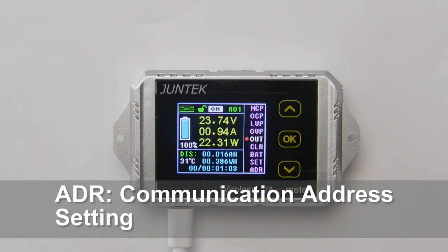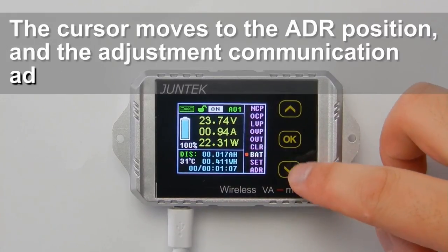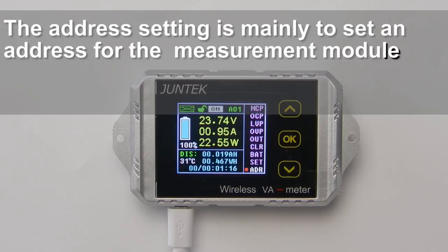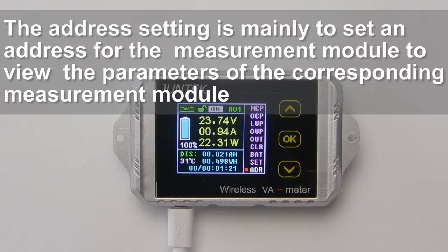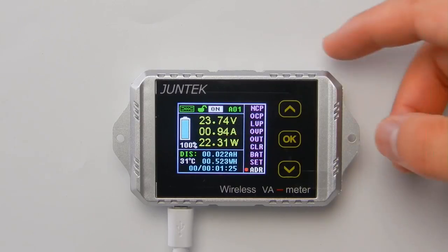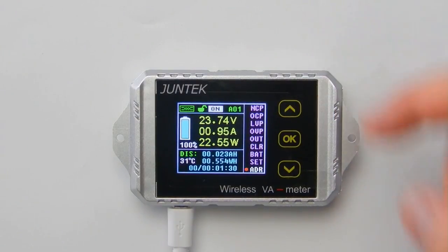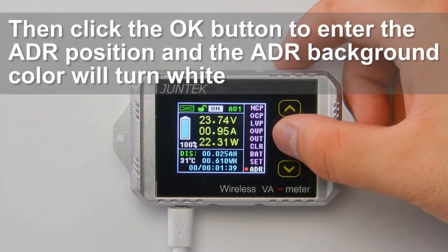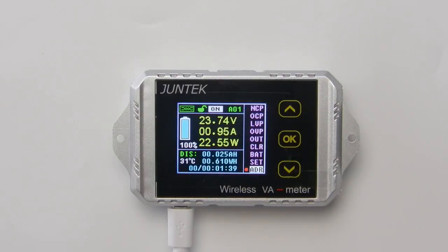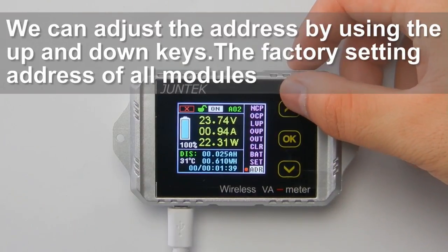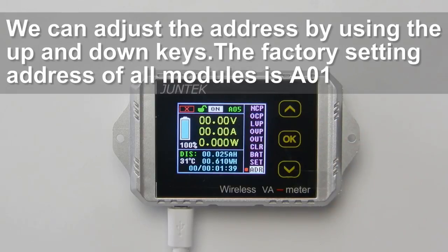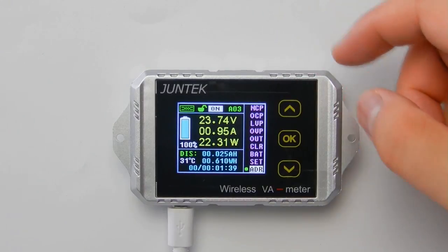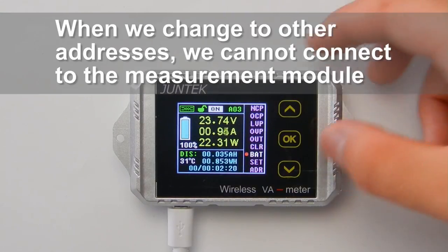ADR — communication address setting. The cursor moves to the ADR position and the communication address is set in wired mode. The address setting assigns an address to the measurement module to view its parameters. Click OK to enter the ADR position — the ADR background color will turn white. Adjust the address using the up and down keys; the factory setting address of all modules is 01. Press and hold OK to complete the setting. When changed to other addresses, the device cannot connect to the measurement module.